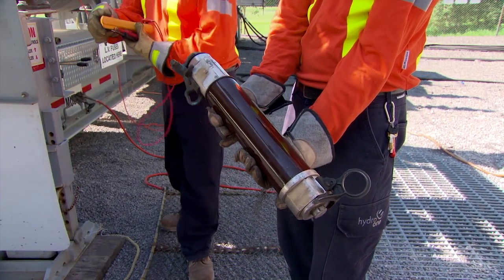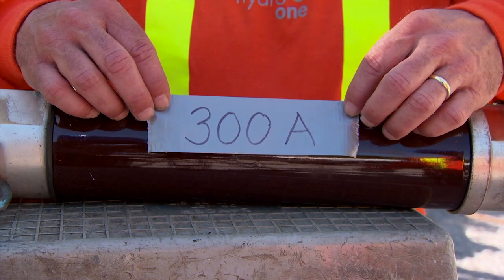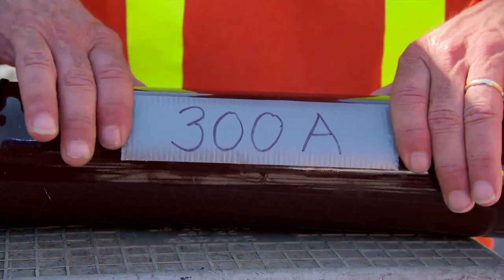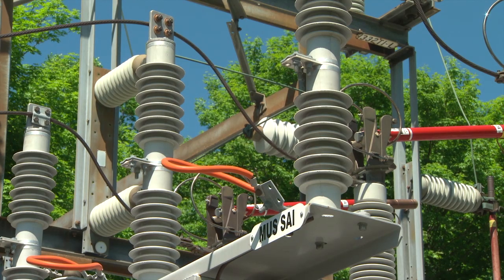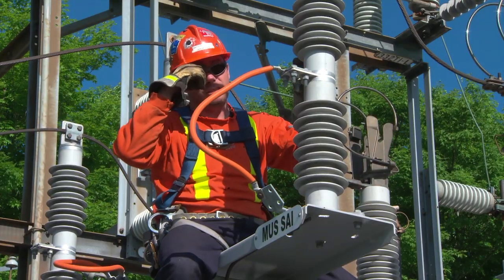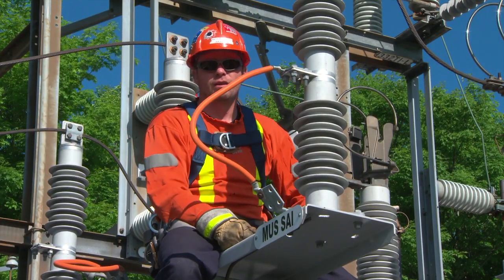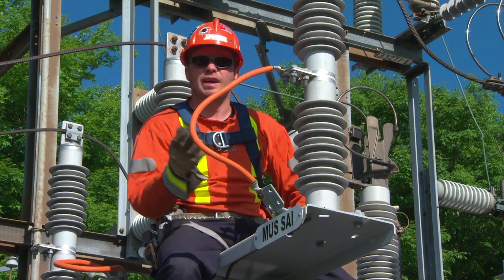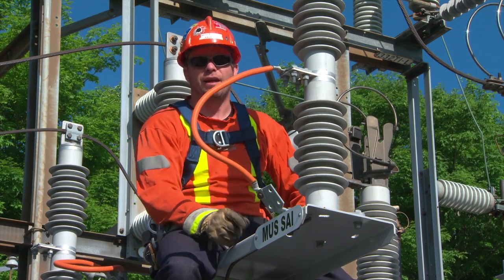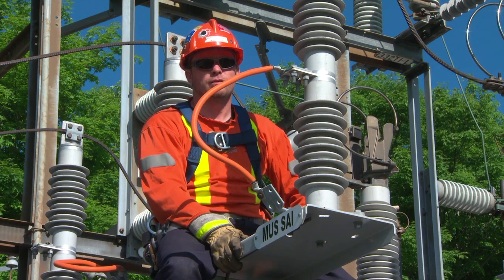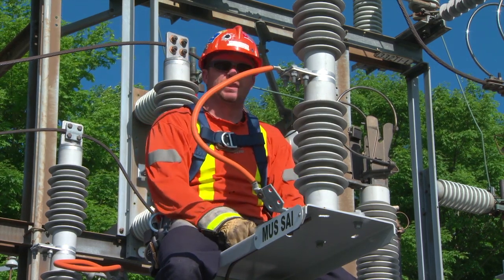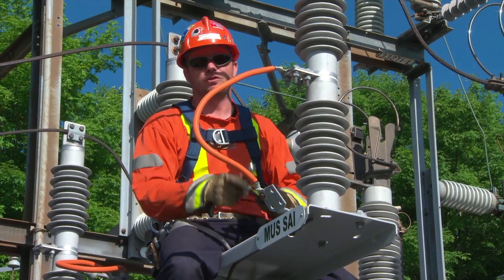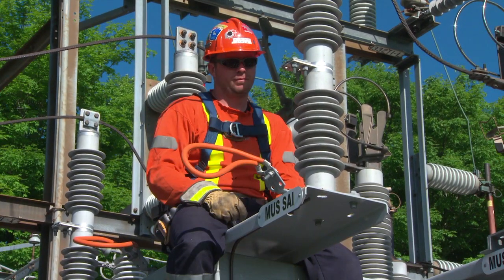27.6 kV class fuses are designed differently. Instead of changing the internal fuse element, you will change the complete fuse body. Ensure that the MUS surge arresters are set to the required operating voltage level. For this installation, the shorting jumpers are disconnected for 44 kV. If the MUS was installed at a 27.6 kV station, then the shorting jumpers would have to be connected.